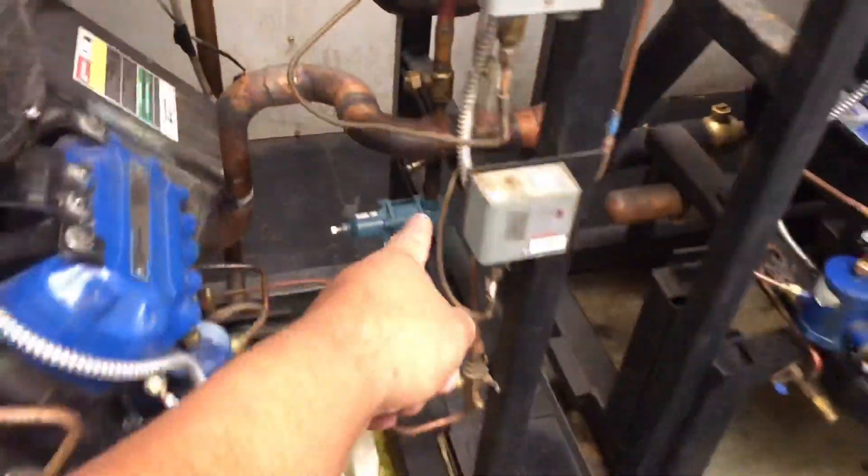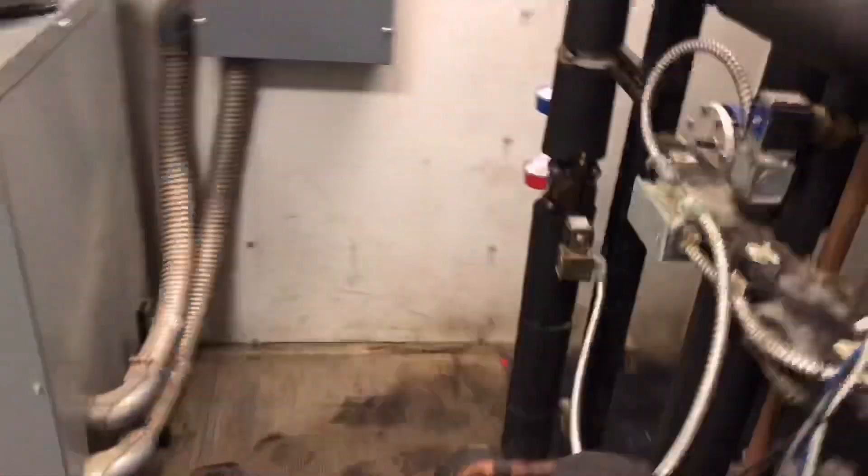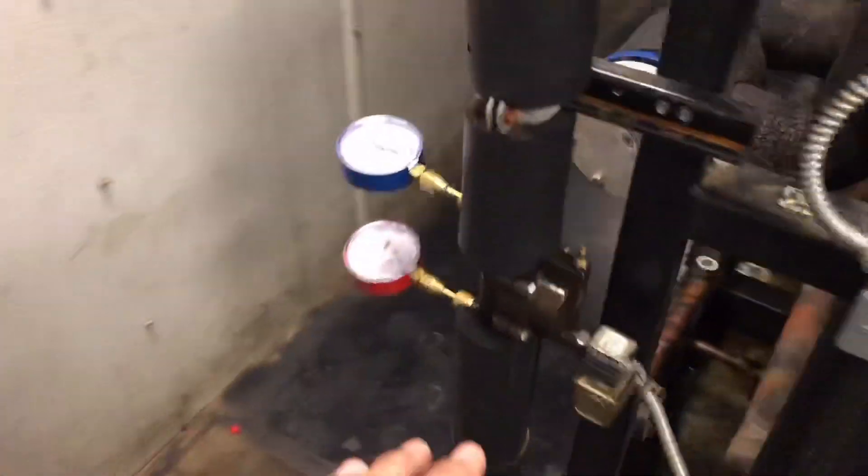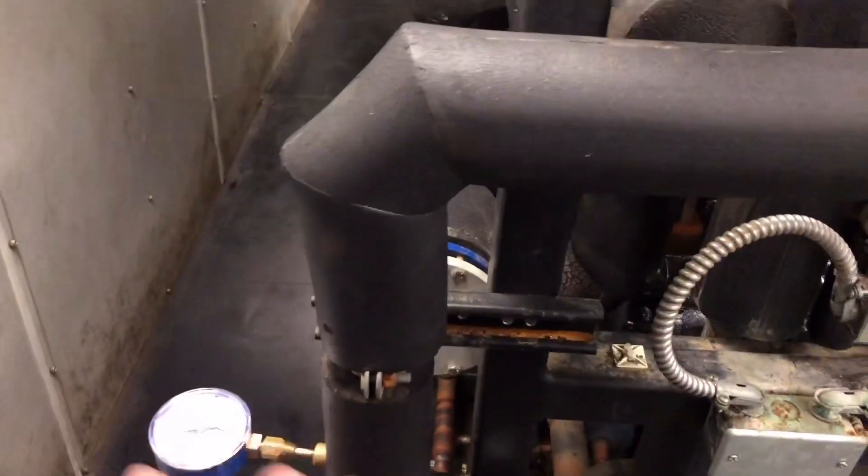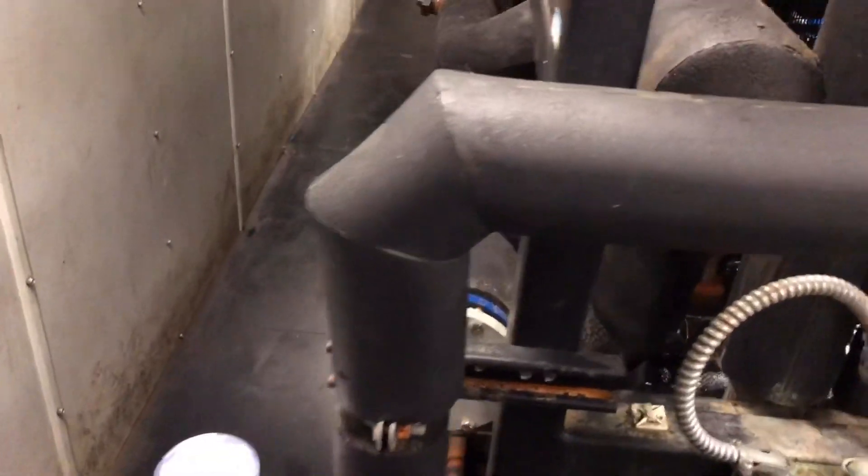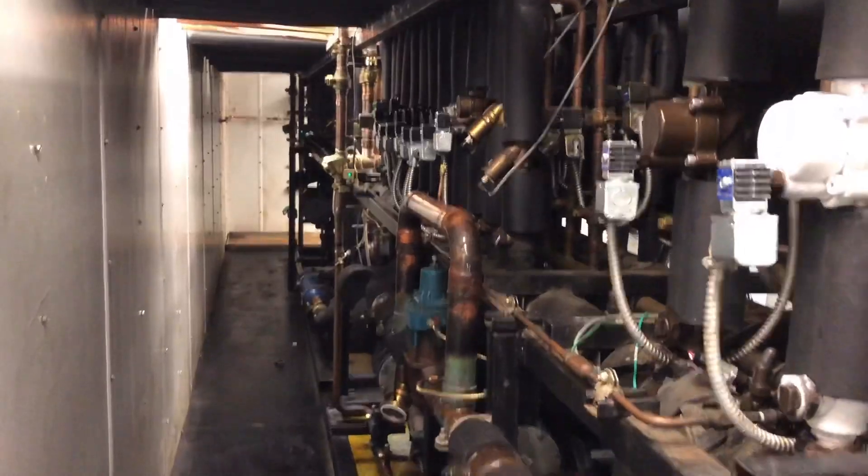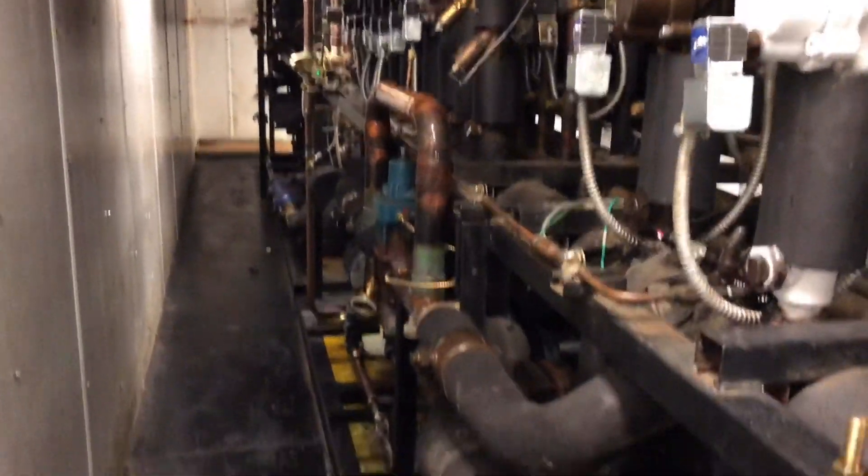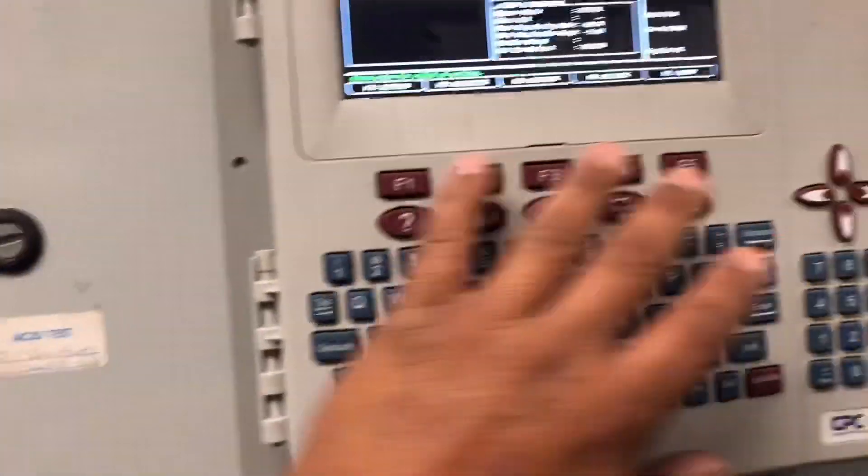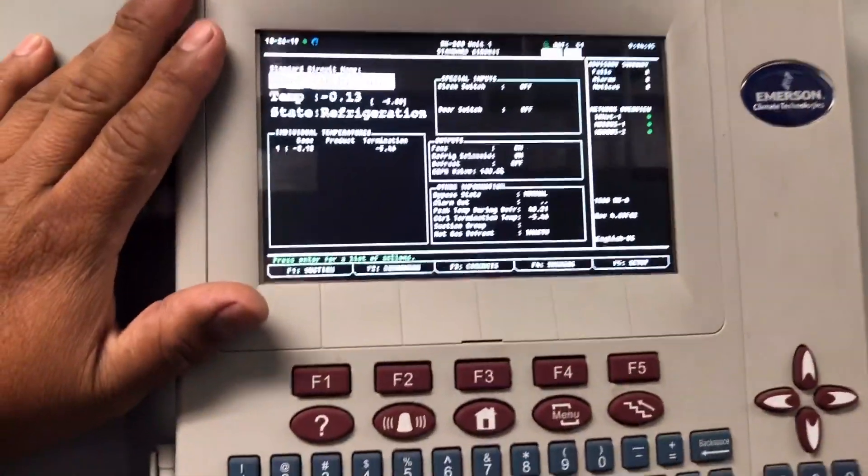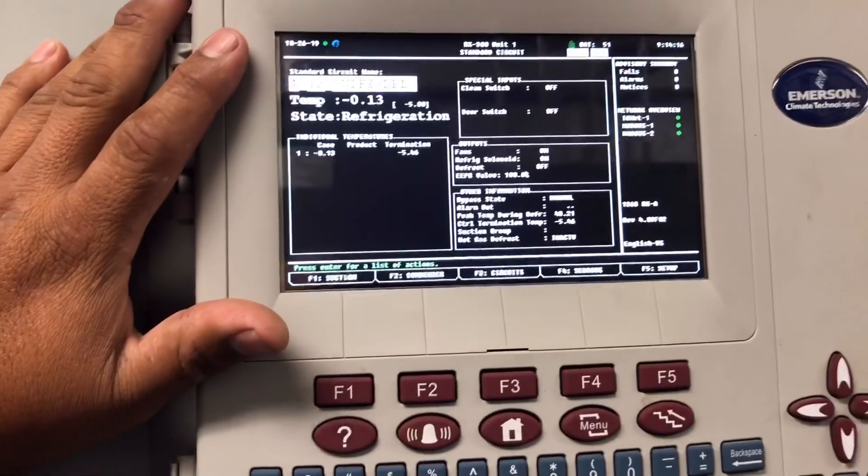See our walk-in freezer. If you go to defrost right there, we're going to try to defrost until the termination temperature reaches 65. But if you have 60 degree or colder saturated vapor going out to the cases and it's turning into a liquid, you're really never going to reach this temperature, not with hot gas, not with a repressurization valve closed. So that's another issue. I know a lot of these things, I just have trouble putting them together right now because this is not a typical residential system.